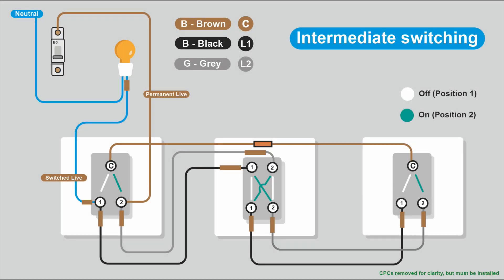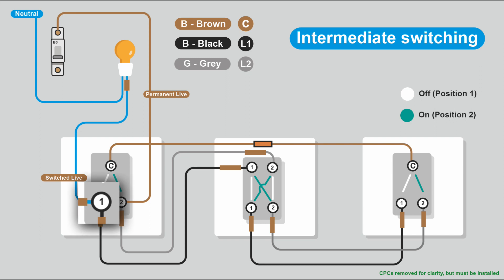This is how we connect power to intermediate switching. The power comes in to connection two and the switch live comes out of the switch and up to the ceiling rose and the light on connection one. So we have a permanent live and a switch live, and we need to connect our strappers.